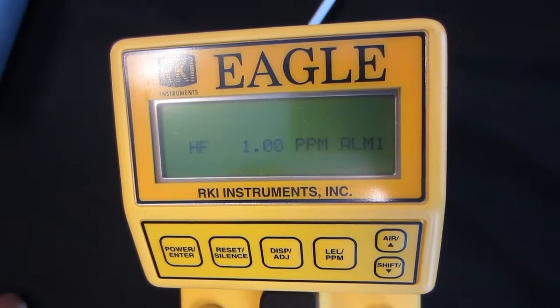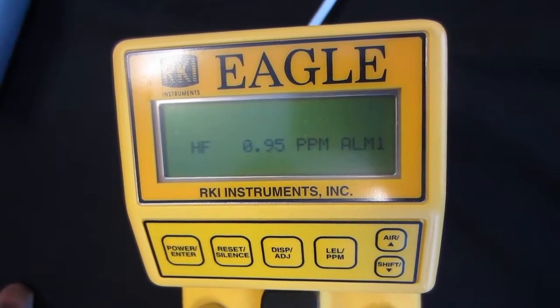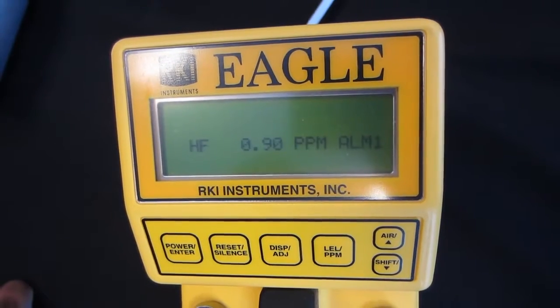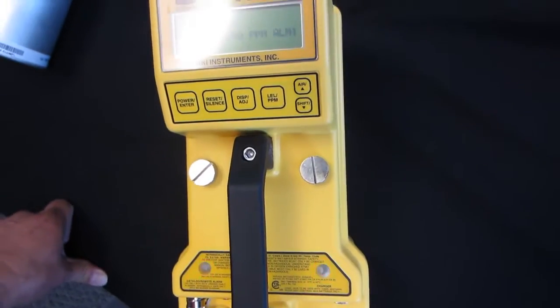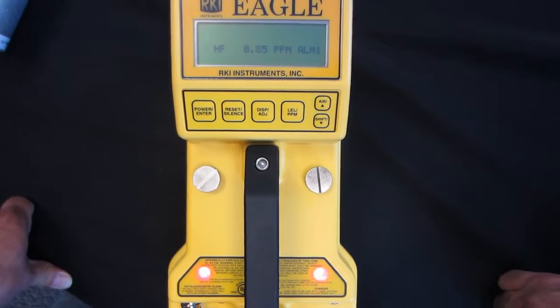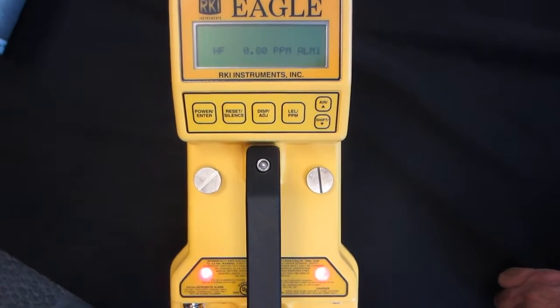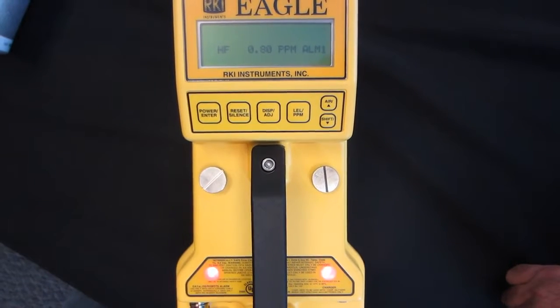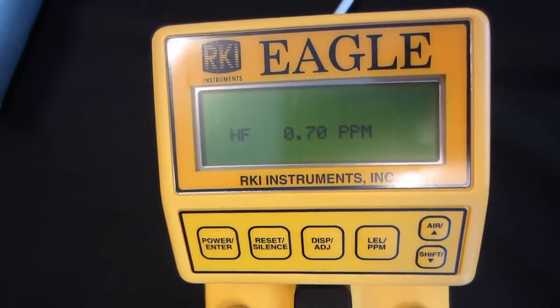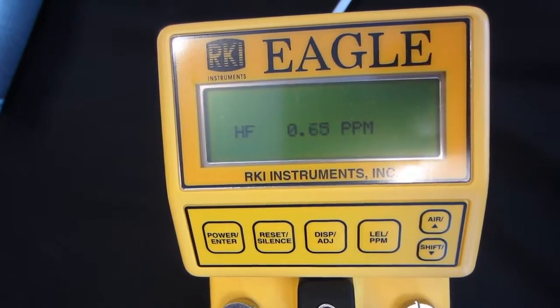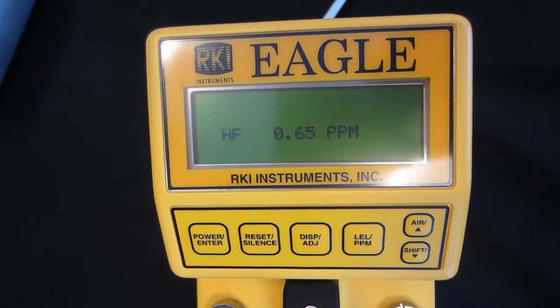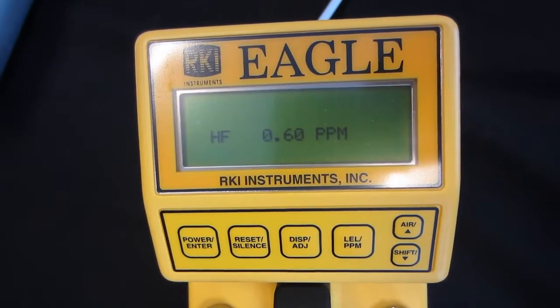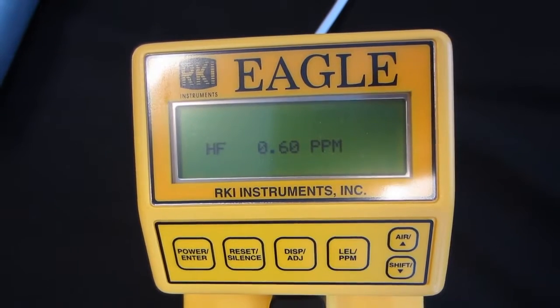The alarms are going off because we still have gas in the flow system, so the reading is coming down steadily. It may take a while for the reading to come down. Right now it's 0.85 and dropping. Once you get below the alarm threshold point, you're able to press the reset silence, and then you're able to silence those alarms. But that will not happen unless you're below the alarm points. So obviously we are, and we were able to silence them.